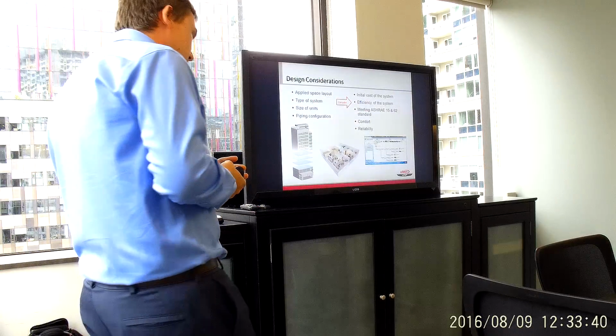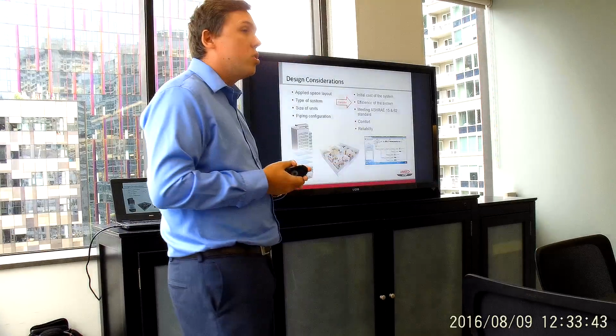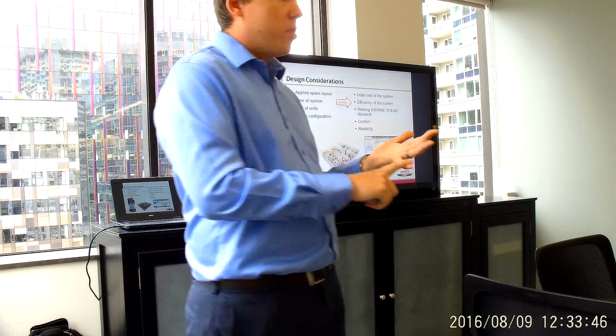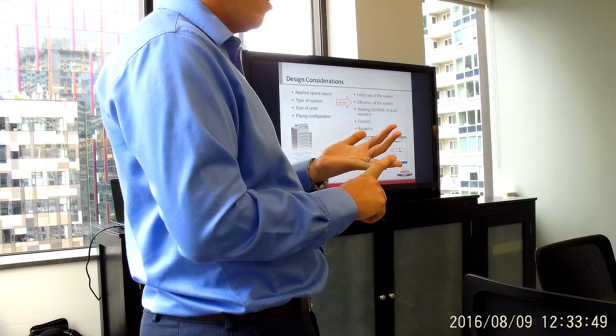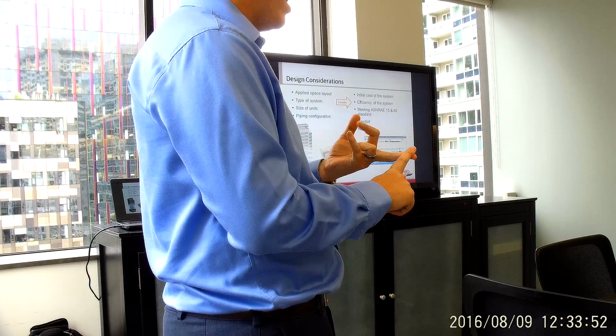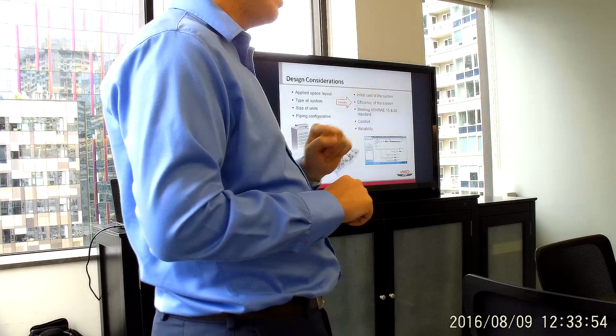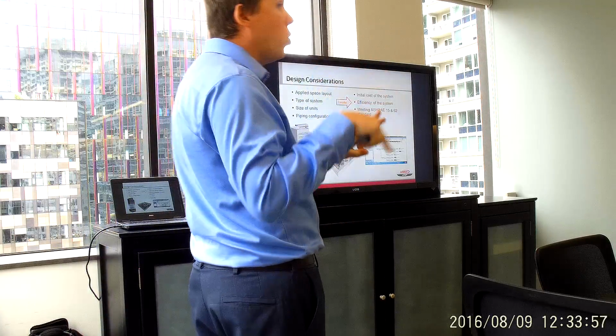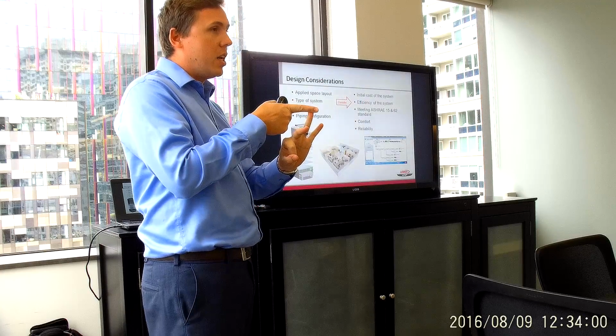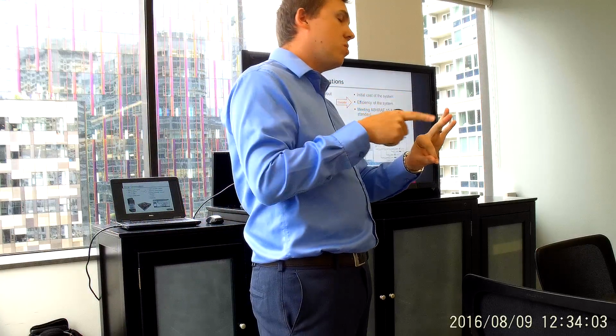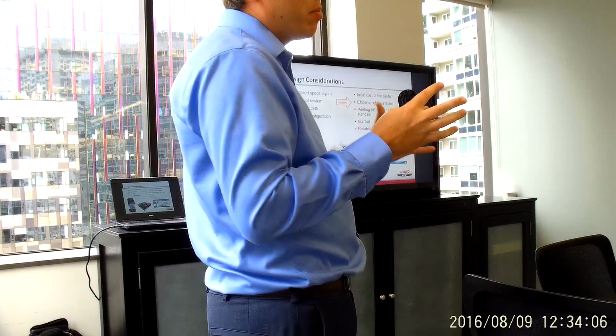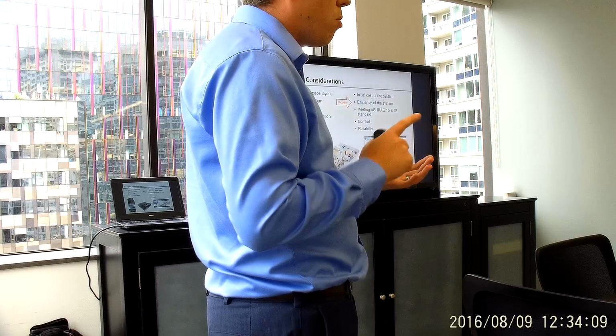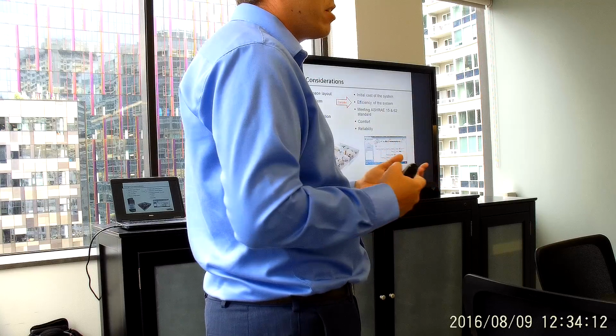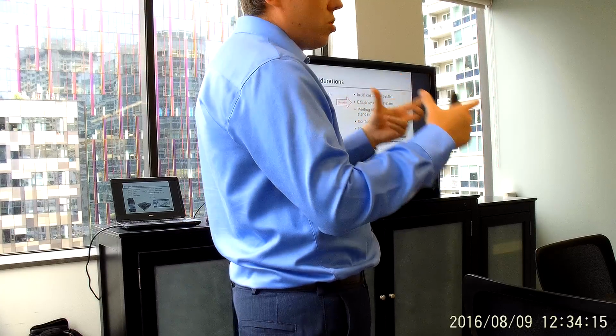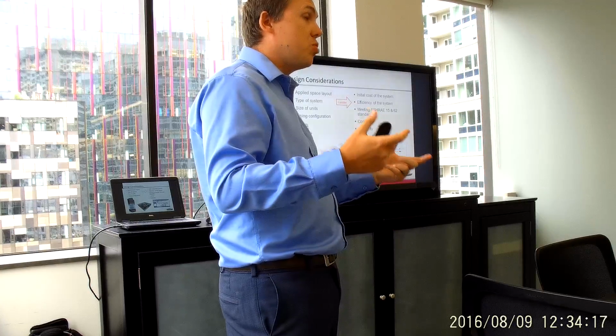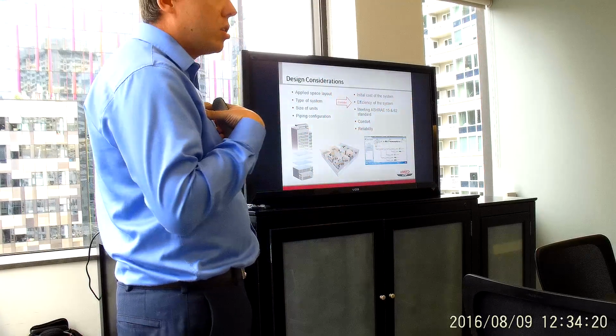We were asked by a large developer in BC to do some comparative pricing between hybrid heat pump, 4-pipe water source heat pumps, and VRF - between those 3 types of systems - to see what the cost comparisons are as a whole, because you've got to take the plumbing into account, the electrical into account, all of these factors. What we found was we were between 7 and 10% cheaper with VRF air cooled. Even though there's more copper piping going into that riser, the fact is those massive water pipes you're running up and down are also extremely expensive and difficult to install. We didn't do that calculation.